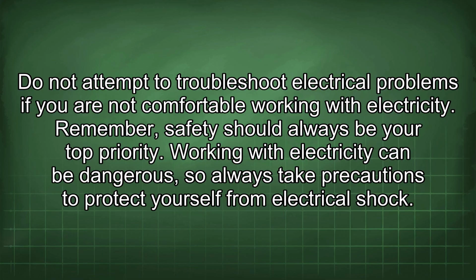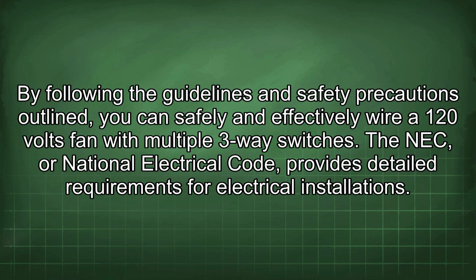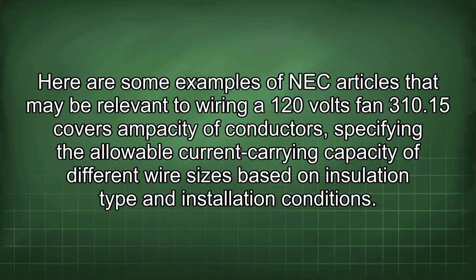Working with electricity can be dangerous, so always take precautions to protect yourself from electrical shock. By following the guidelines and safety precautions outlined, you can safely and effectively wire a 120 volts fan with multiple three-way switches. The NEC, or National Electrical Code, provides detailed requirements for electrical installations. Here are some examples of NEC articles that may be relevant to wiring a 120 volts fan. 310.15 covers ampacity of conductors, specifying the allowable current carrying capacity of different wire sizes based on insulation type and installation conditions.